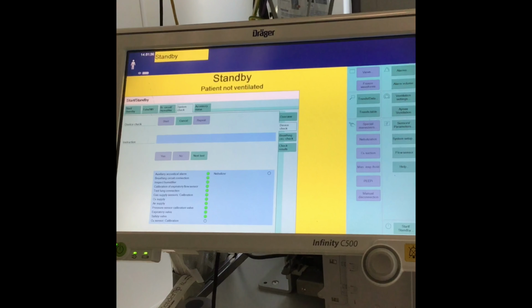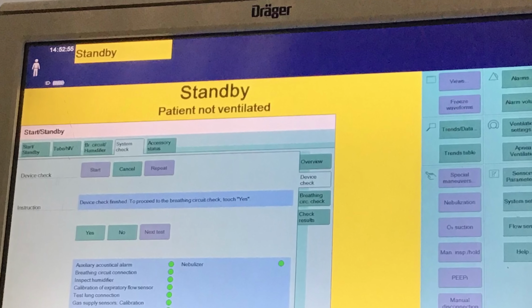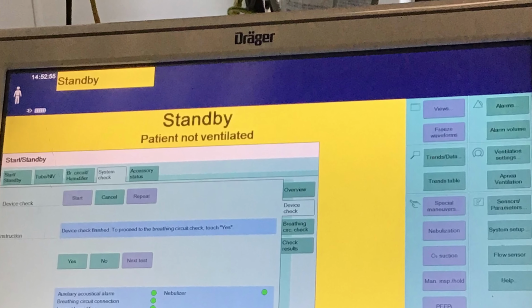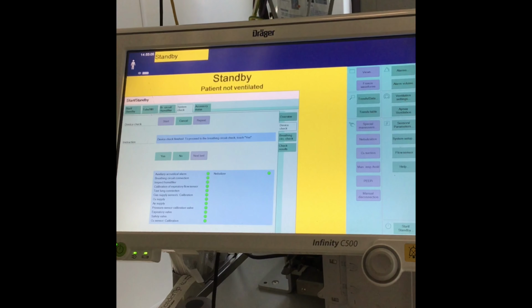You see that it's then making its way through the rest of the tests. And you're just waiting for all of the green lights to appear in the circle. So once the ventilator has passed all of its checks, you can see there that all of the green lights are in the circles. The next prompt in the instruction panel is that the device check is finished and you can proceed to the breathing circuit check.